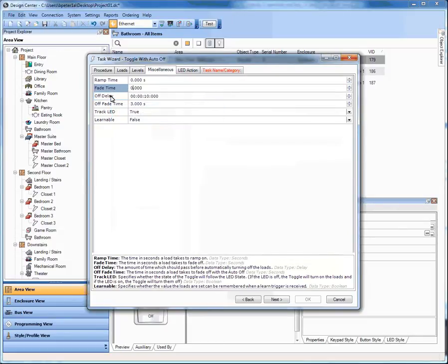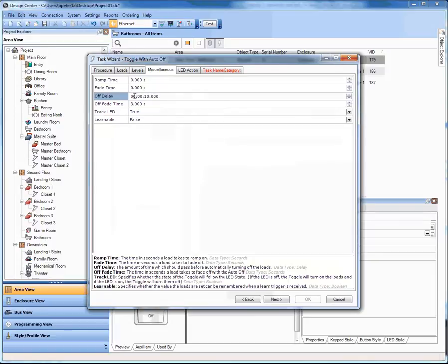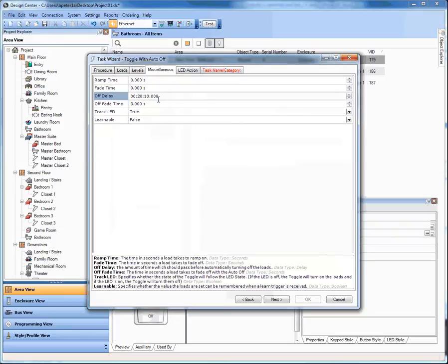And in this next field, the off delay, I have hours, minutes, seconds, and milliseconds in these four sections left to right. So what I'm going to do is make this have an off delay of 20 minutes, meaning it will wait 20 minutes after I press this button before it turns off that load. It will still turn off with the toggle, but this will be the auto off portion of it.